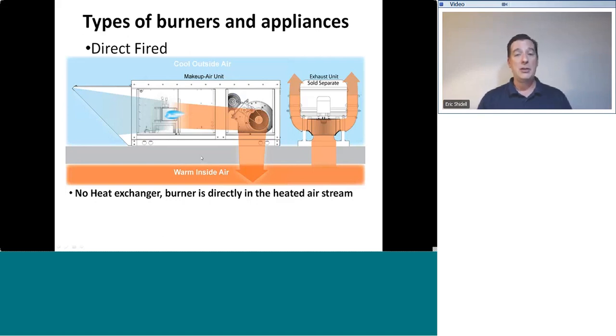Instead, the burner is modulating. And a modulating burner has been in use on direct fire appliances for generations, essentially. So the thermostat looks at the discharge air temperature, compares it to what the discharge air temperature set point is, and then it modulates the firing rate of the burner accordingly. So say, for example, it's 60 degrees outdoors, and the discharge air temperature set point is 70, it will modulate the flame to be a very, very low, small flame, only the amount required to raise that air temperature 10 degrees as it passes through the unit.